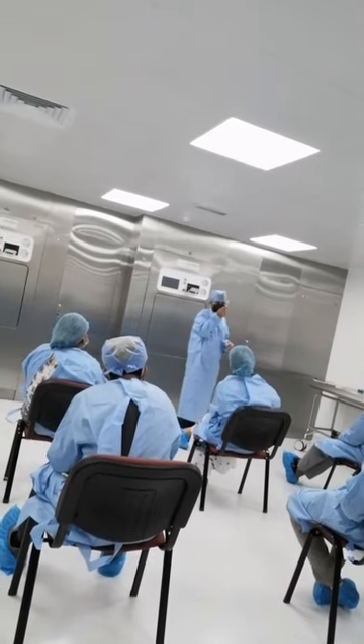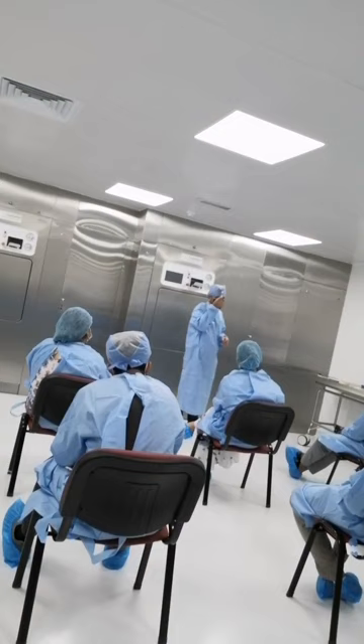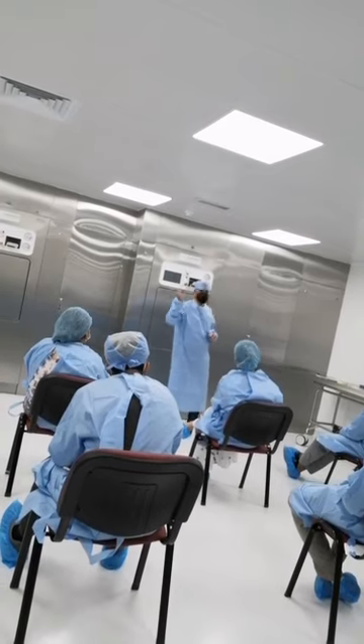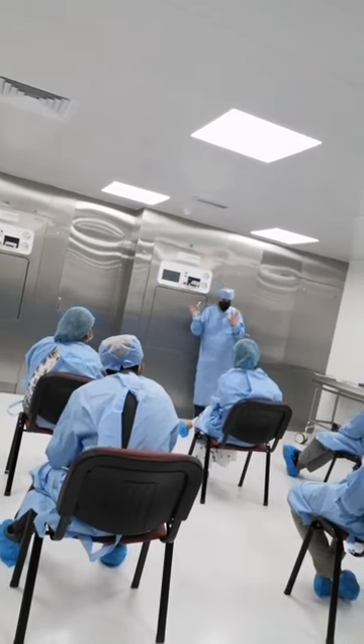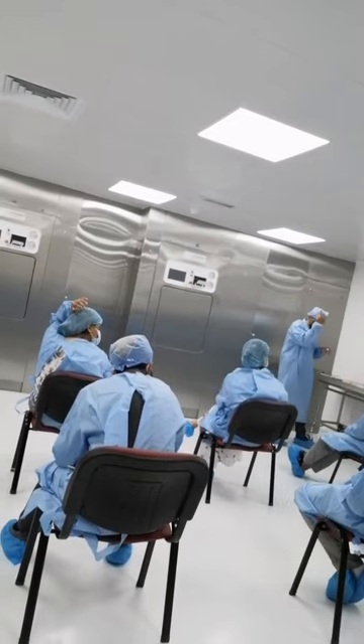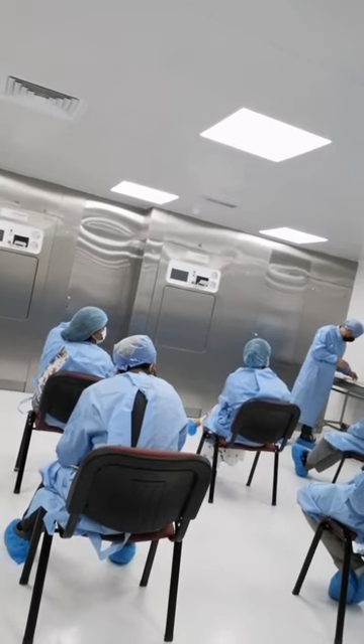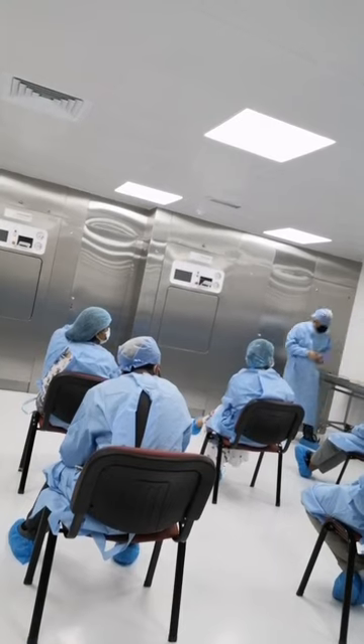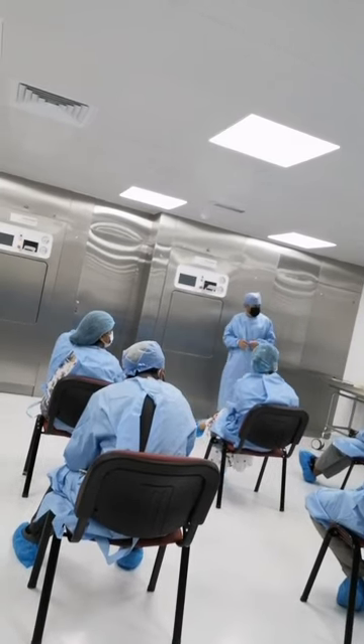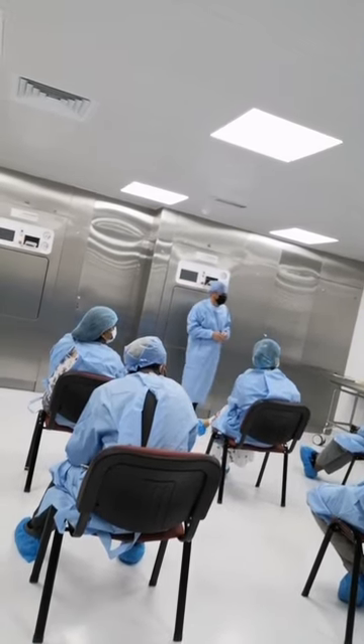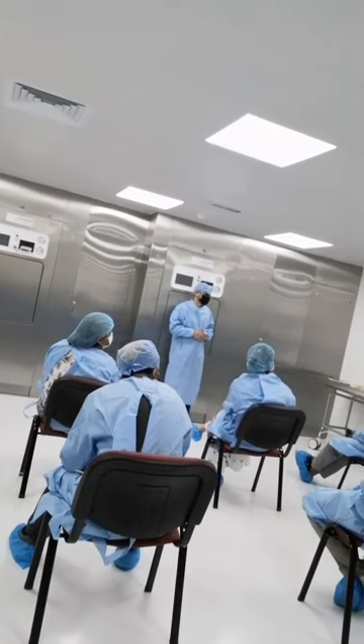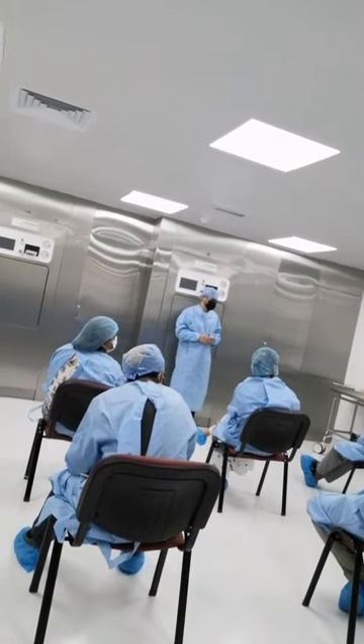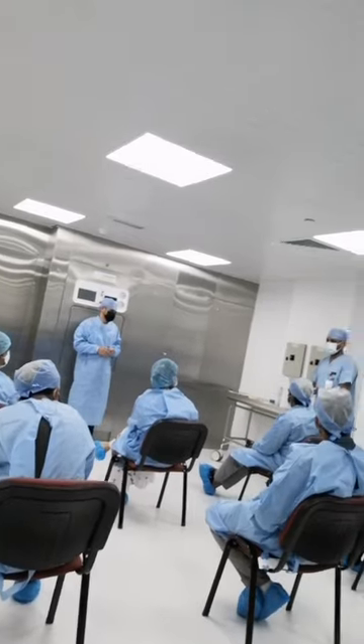But in my whole life, I didn't see a biological indicator failure because of the machine, not even once in my life. And I've seen once there was a failure, it was wrongly processed. The indicator was not crushed. This is what I found. You got the background from outside, where I found that it was not crushed. So they processed it, and it failed.